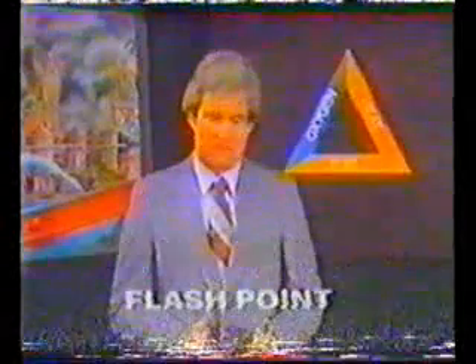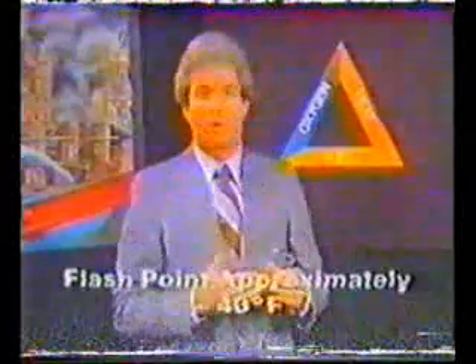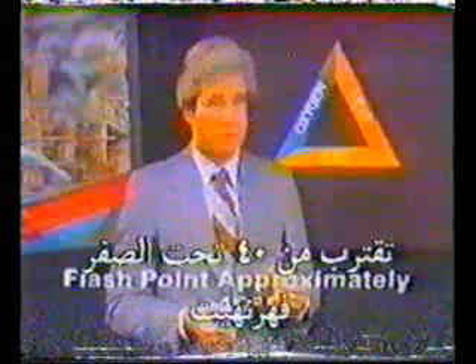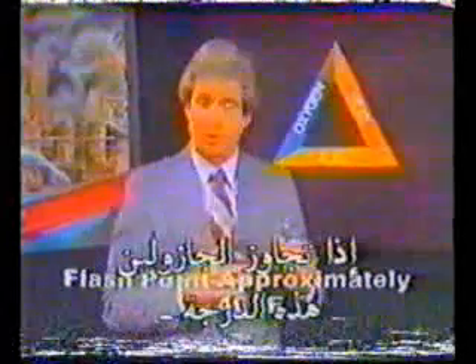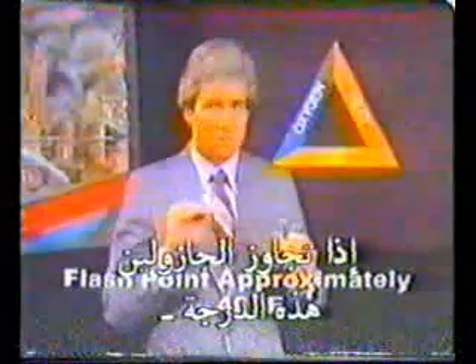Another important characteristic of a fuel is its flash point. Flash point is the temperature at which a liquid gives off sufficient vapors to form a flammable mixture. Gasoline has a very low flash point, somewhere in the neighborhood of 40 degrees below zero Fahrenheit. So, whenever gasoline is above this temperature, it will release ignitable vapors.